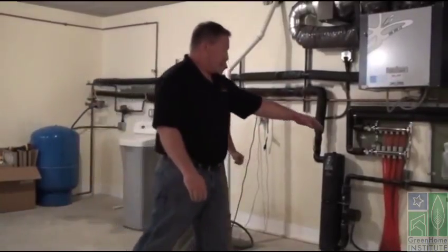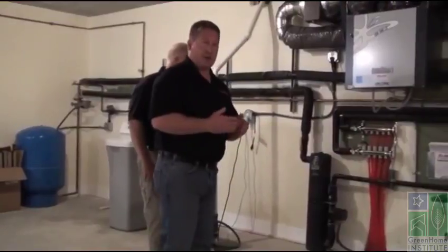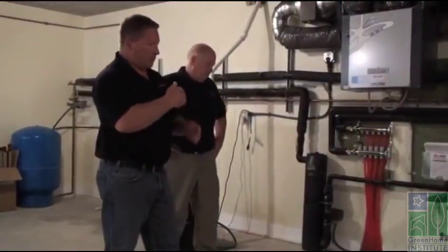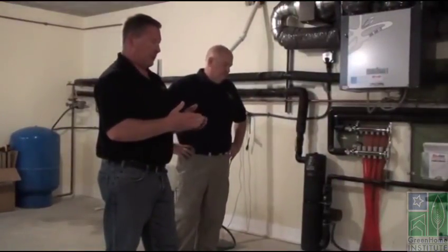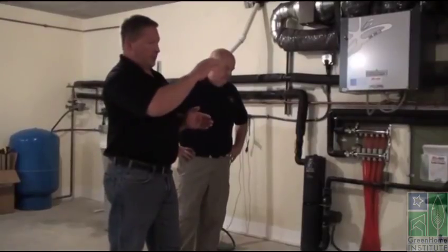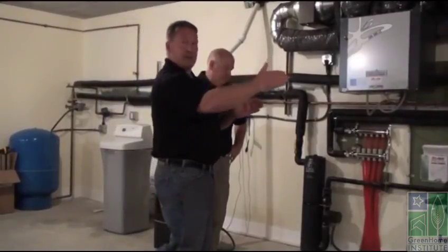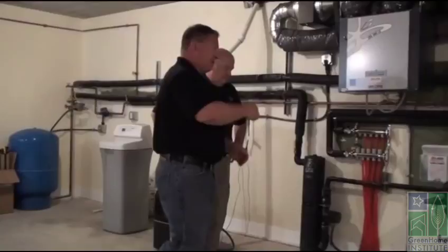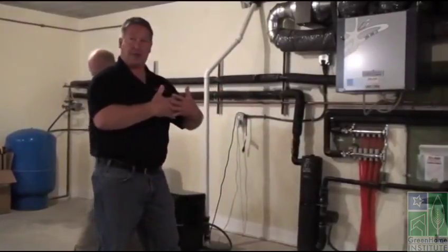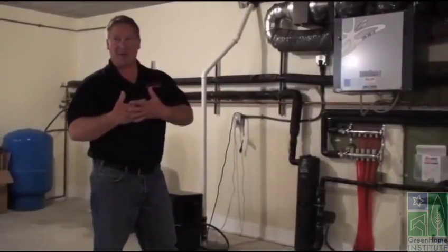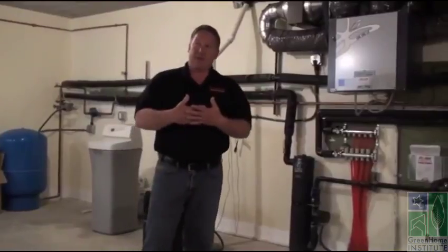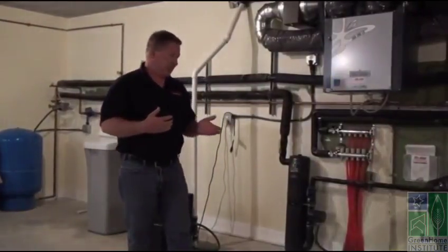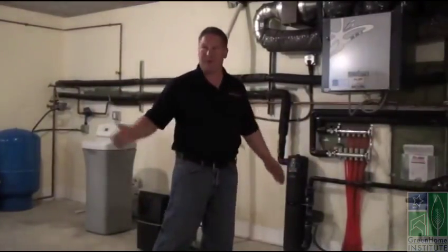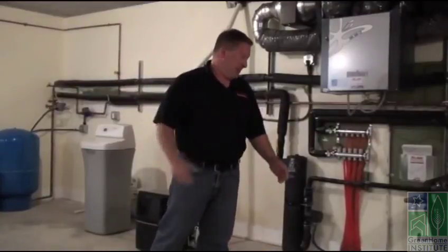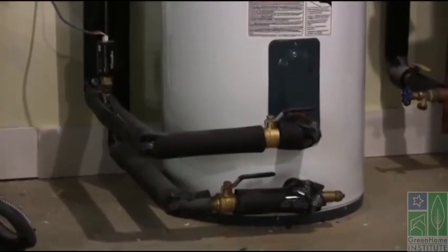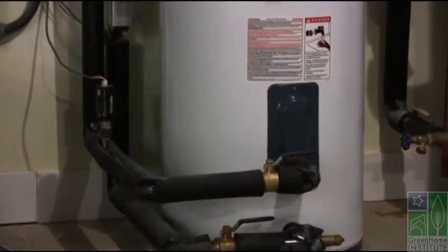Once that water comes into the heat pump, there's a heat exchanger there that the water goes through, and either the water in the house, which is a separate system, they're separated by that heat exchanger, passes through each other and gives up or picks up heat depending again on which mode you're in. So if you're in the heating mode, it's going to extract the heat out of the water that's been picked up from the earth and transfer that heat into the water that goes into this buffer tank.